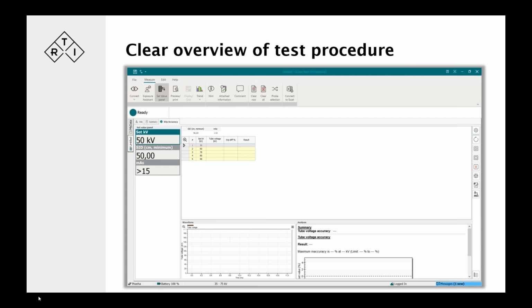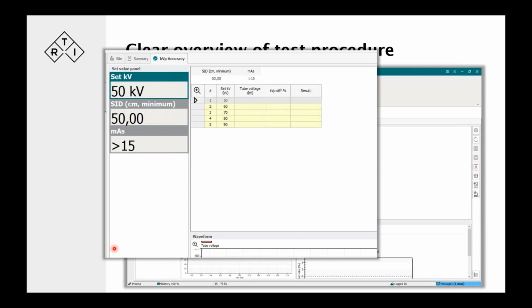Some of you may have seen Ocean before, but this is a bit of a new view where we're looking at a test view, giving us the possibility to have the set values as a panel to the side with a slightly larger font. So that's easier for us to see it from a bit of a distance. And it shows the set values for the row we're at. In this case, we're looking at a kVp accuracy test for 5 exposures, 50, 60, up to 90. SID should be 50 centimeters. This could be at any distance. The mAs needs to be larger than 15. And what happens here is that we have the tube voltage collected from the instrument, Piranha or Cobia. The software will calculate the difference in percentage between the measured value and the set value and give us a result, pass or fail.